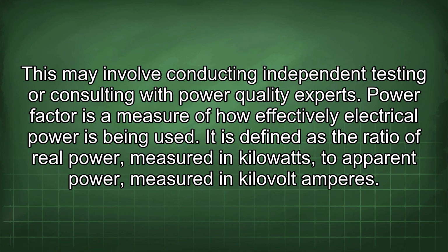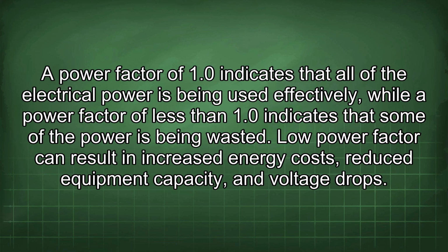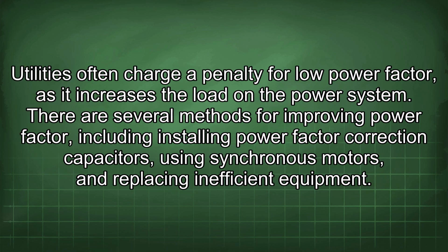Power factor is a measure of how effectively electrical power is being used. It is defined as the ratio of real power, measured in kilowatts, to apparent power, measured in kilovolt amperes. A power factor of 1.0 indicates that all of the electrical power is being used effectively, while a power factor of less than 1.0 indicates that some of the power is being wasted. Low power factor can result in increased energy costs, reduced equipment capacity, and voltage drops. Utilities often charge a penalty for low power factor as it increases the load in the power system.